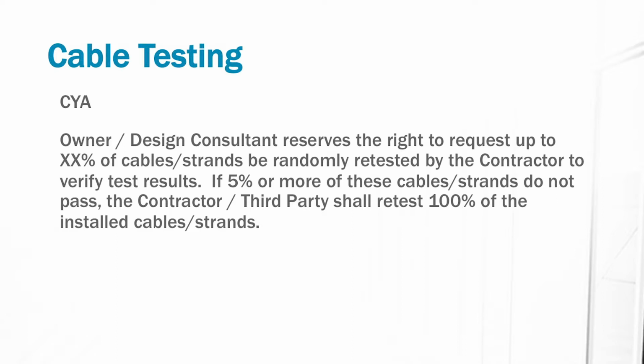Another thing I write into my cable testing specs is to reserve the right to ask for retesting. Another way around that is to invite me, as the design consultant, or the owner, to view your testing. Tell me when you've got that scheduled, give me a week in advance, and maybe I'll present myself to observe you doing the testing. Another way is to stipulate that on your final punch walk, you provide two technicians with the testers available for two hours, and I can have them spot test up to a certain percentage of cables.